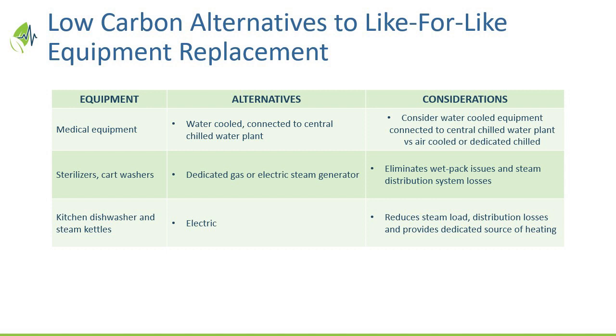All of your chilled water systems, if you have them—there's a couple of hospitals that don't—will all be running year-round in the future, because that's the system that goes galloping around the hospital and collects up all those bits of heat here, there, and everywhere, and comes back to your new heat recovery chiller, which you're using to heat the hospital. So hospitals have a huge amount of internally generated heat. It all has to be captured.